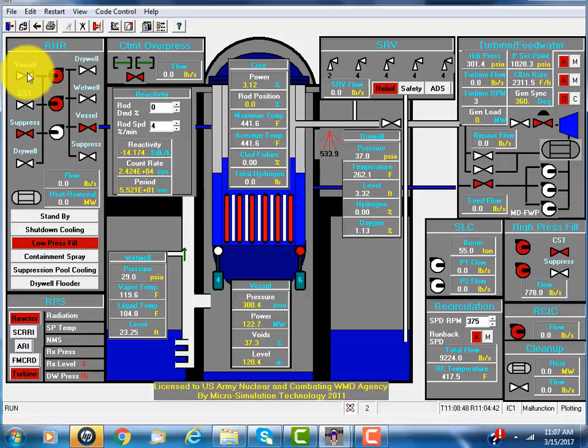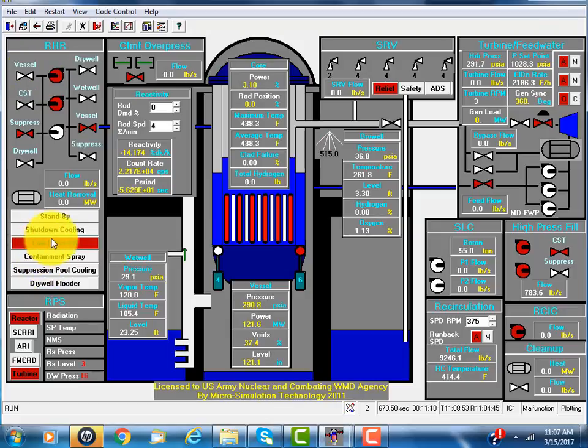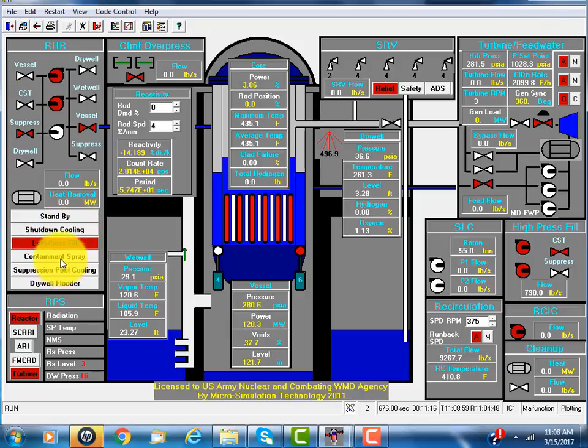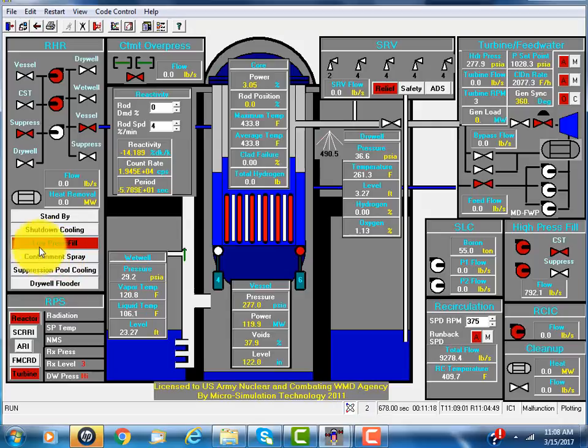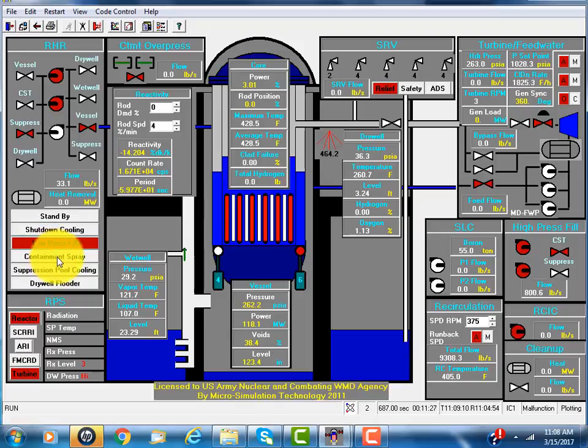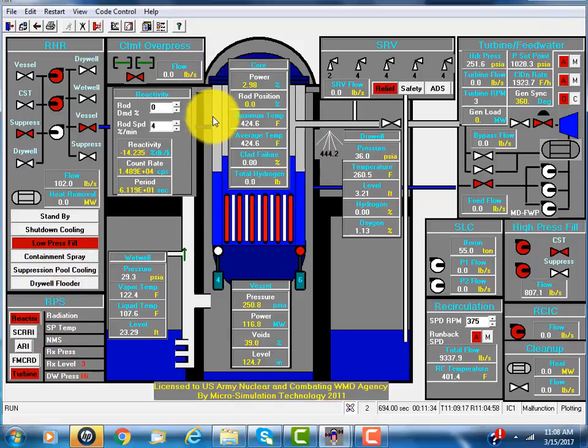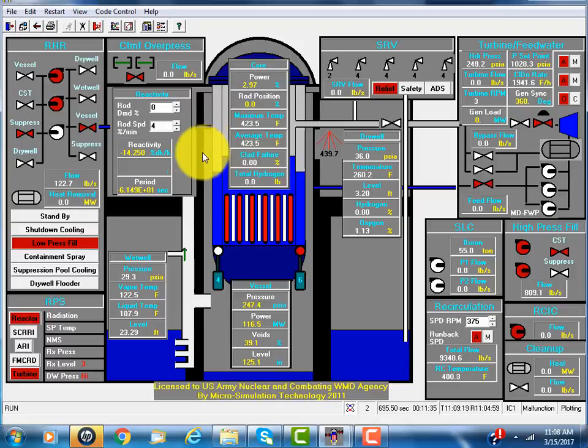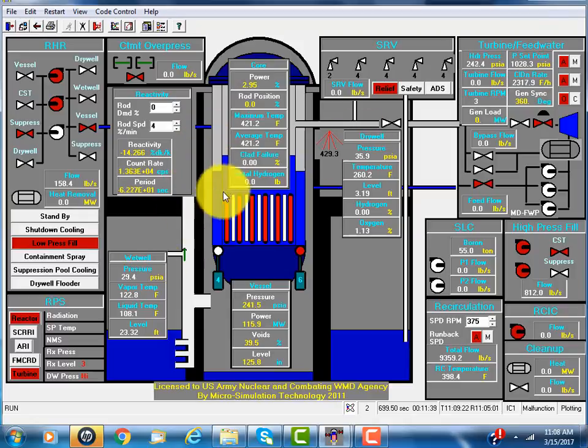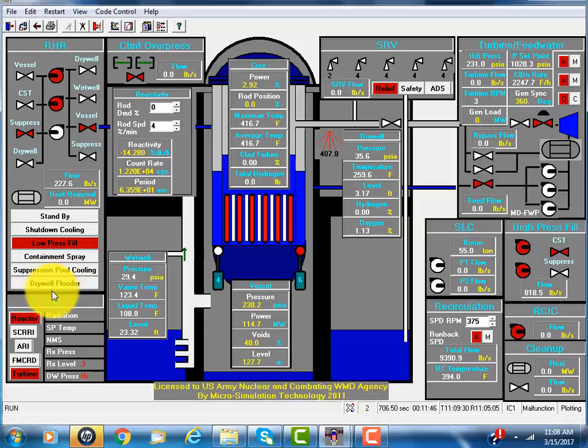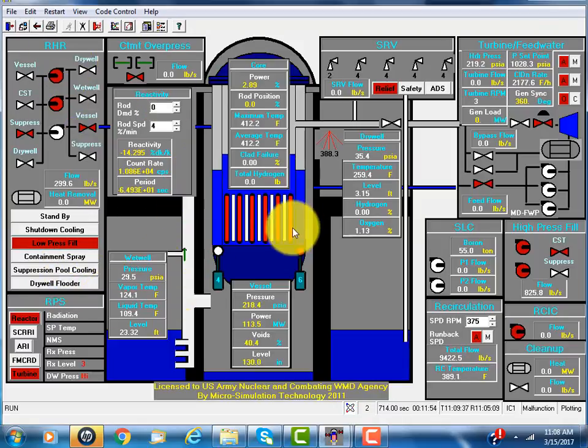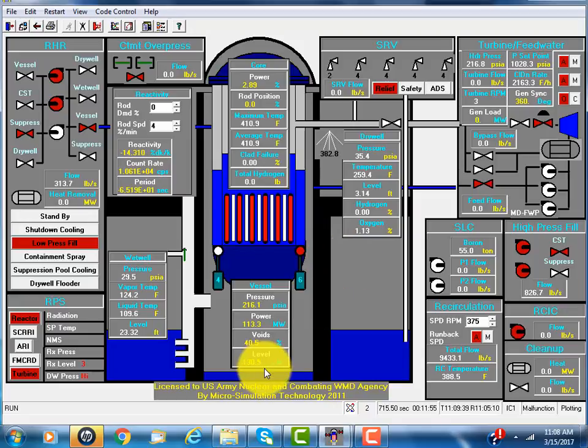The emergency core cooling has many different modes. The shutdown cooling mode for normal shutdown cooling. Right now, that's the low pressure injection mode. There's also containment spray. It takes water to spray in the containment to reduce the pressure. And there's a suppression pool cooling mode. Those are multiple layers of protection of the ABWR.